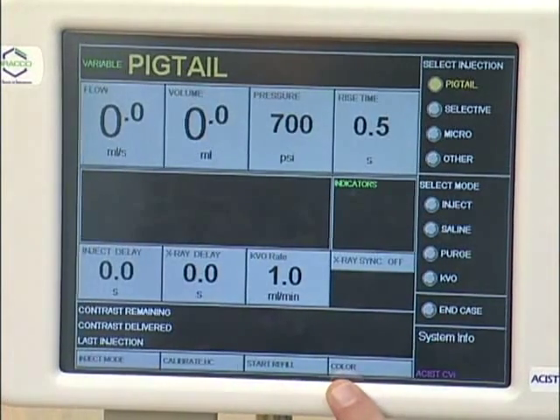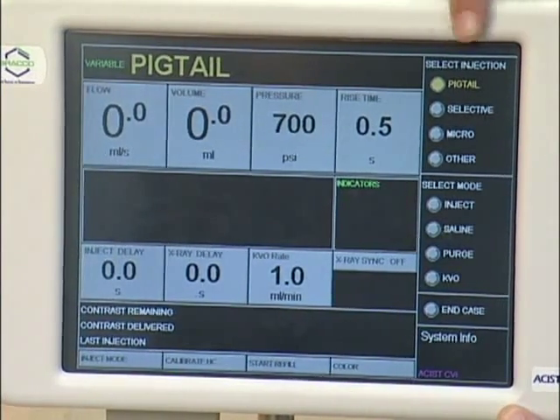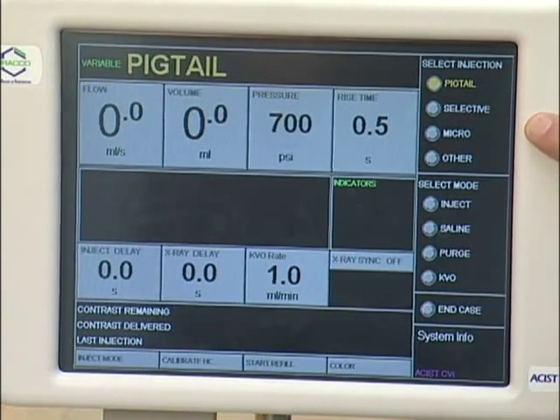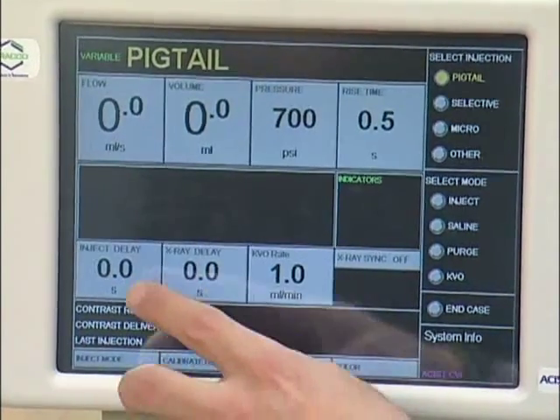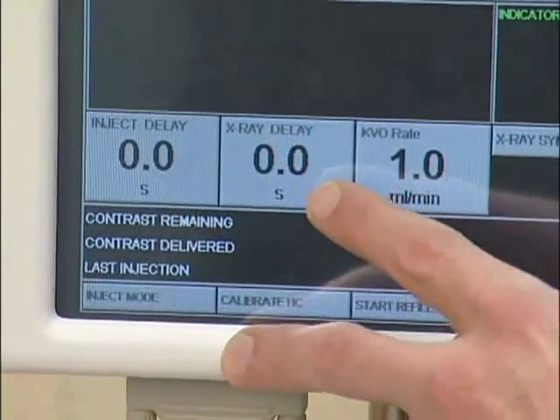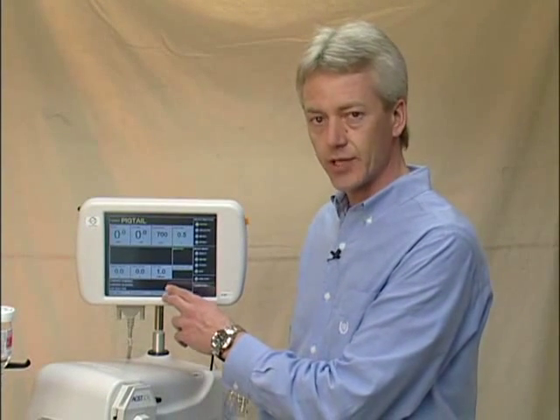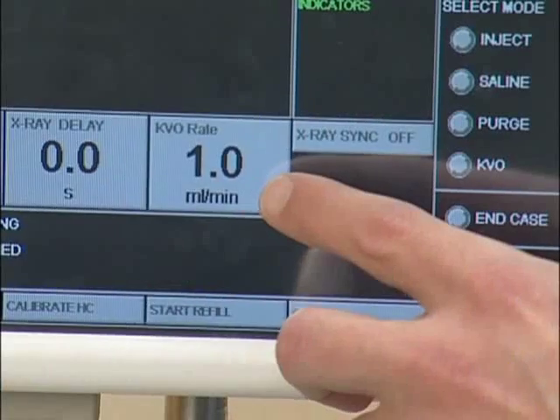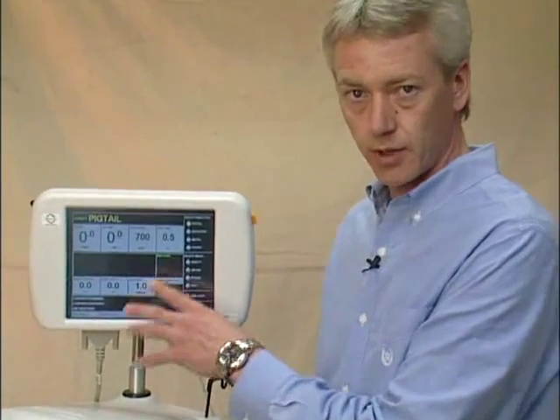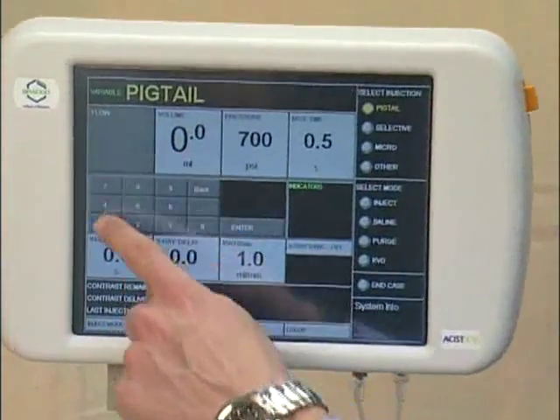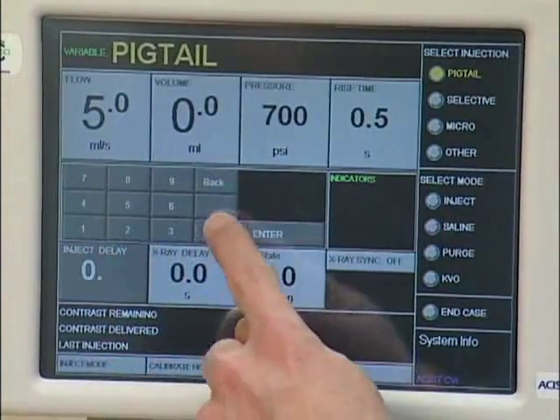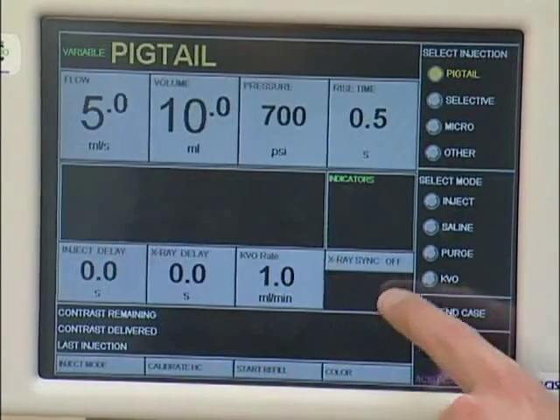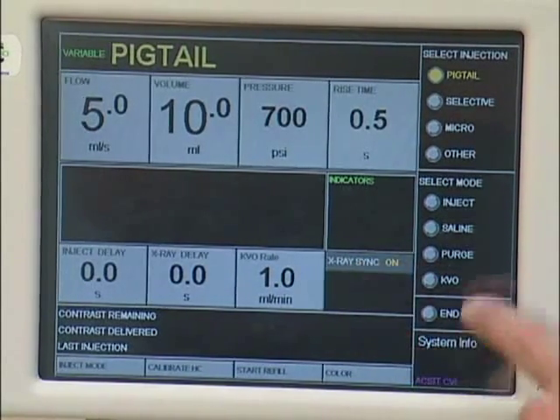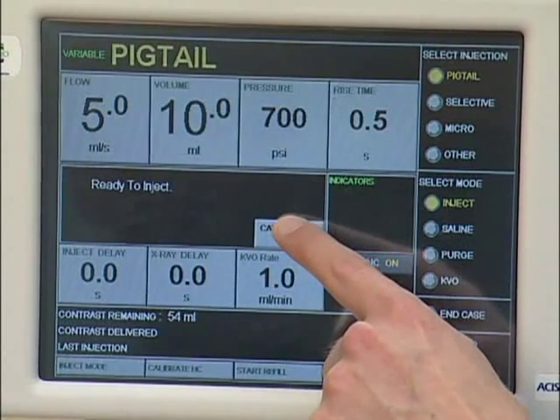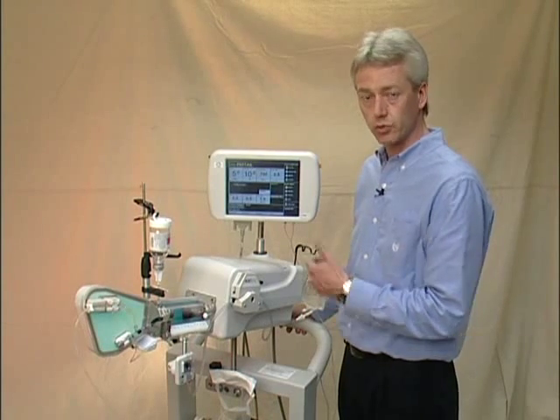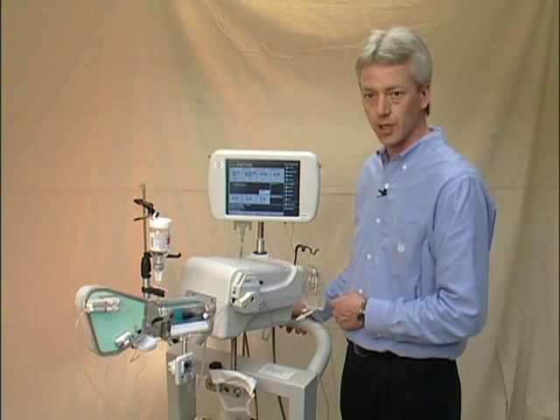There's a few extra functions on our peripheral mode of the CVi. As you can see, instead of left coronary or right coronary, we have the catheter types in the upper right box. In the center, you'll see the settings for the delay of the X-ray and the delay of the injection. The KVO function is keep vessel open, which provides a slow pulse of saline at the selected rate by the operator. To arm the system in a synchronization mode, we will first set the appropriate parameters. We'll turn the synchronization button on and then arm the system to inject as we would normally. Now the system is able to be remote controlled injected from a Siemens, GE, Toshiba, or Philips hand switch in the control room.